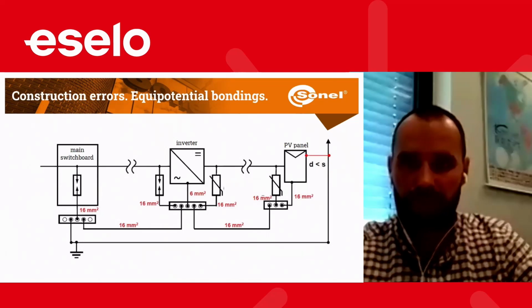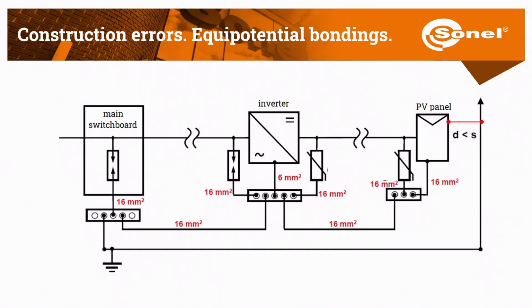Construction errors are also made with the wrong choice of, for example, the diameter of the cables. Many installers make the connections only with, for example, 6 millimeter square cables. In some cases, it might not be enough. So this is something we have to check during, for example, the visual check of the installation before the measurements.